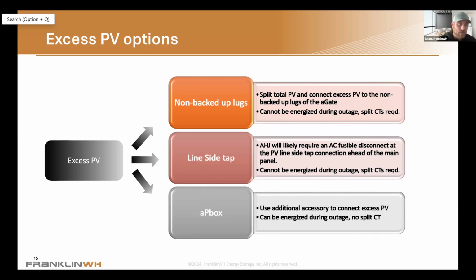If I do that, I need to use a split CT connector that you can purchase from BayWa. Just a heads up, anytime we're landing on non-backed up lugs, we need to use an external split CT -- same thing with the line side tap.